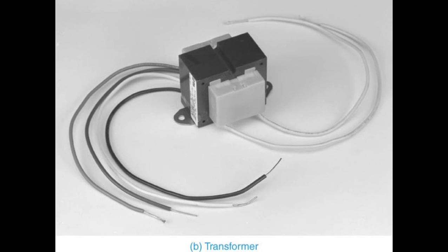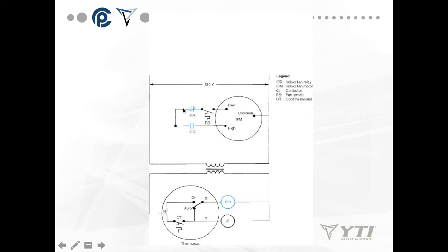This is an example of a multi-tap transformer. Okay, your two secondary leads are on one side of it. That's where your 24 volts come from, your two secondary leads. Then you might have four primary leads. That white is usually going to be the common. So that would go to L2. And then depending on what voltage you're using, you will use one of these other leads and you will individually wire cap the others. And if you look at this transformer on the side of it, there's a label that will tell you what wires to use for what voltages. It's pretty easy to mark.